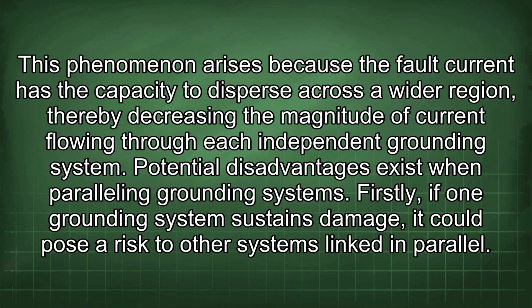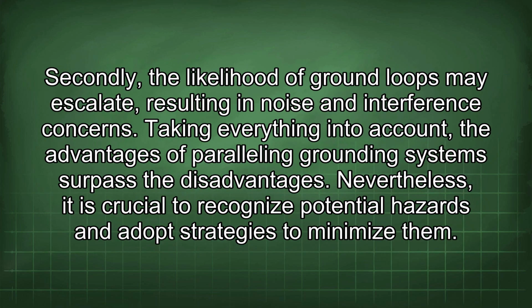Potential disadvantages exist when paralleling grounding systems. Firstly, if one grounding system sustains damage, it could pose a risk to other systems linked in parallel. Secondly, the likelihood of ground loops may escalate, resulting in noise and interference concerns. Taking everything into account, the advantages of paralleling grounding systems surpass the disadvantages. Nevertheless, it is crucial to recognize potential hazards and adopt strategies to minimize them.